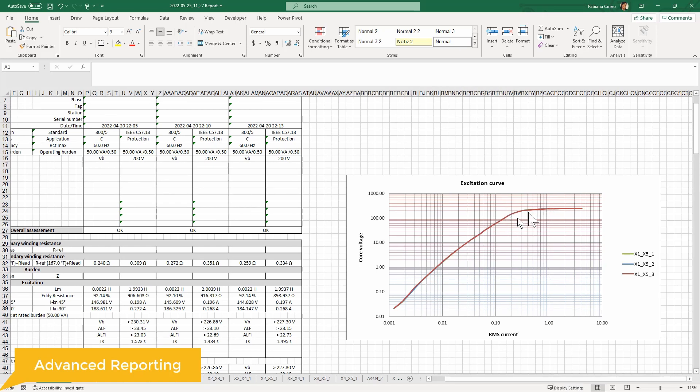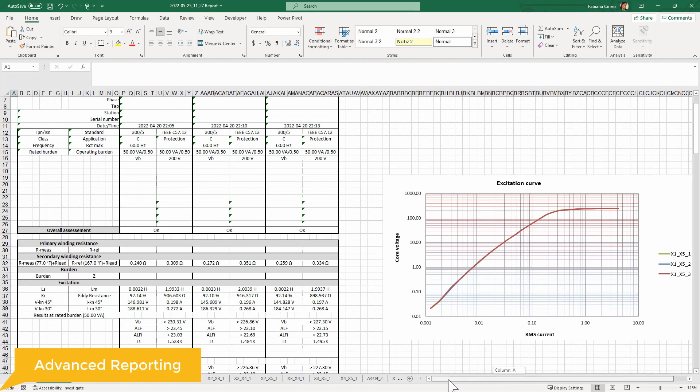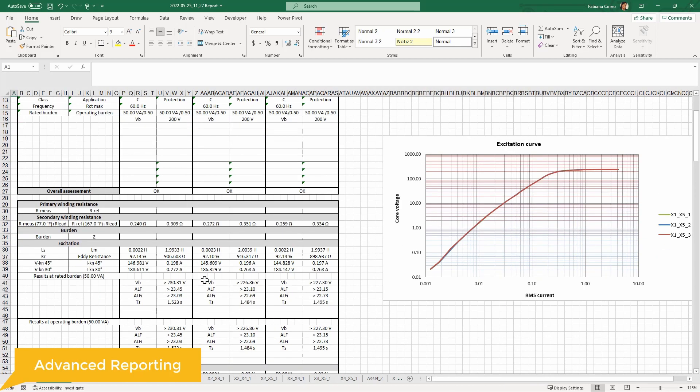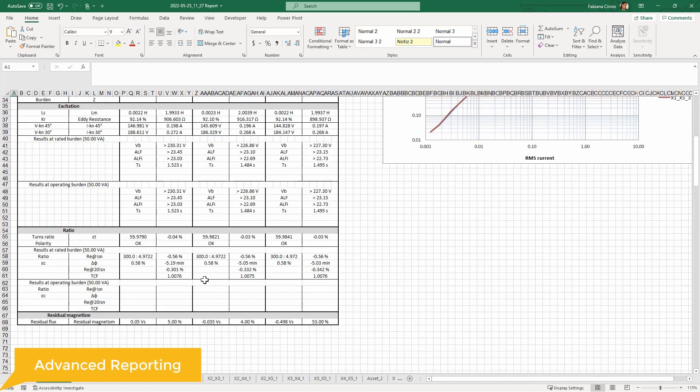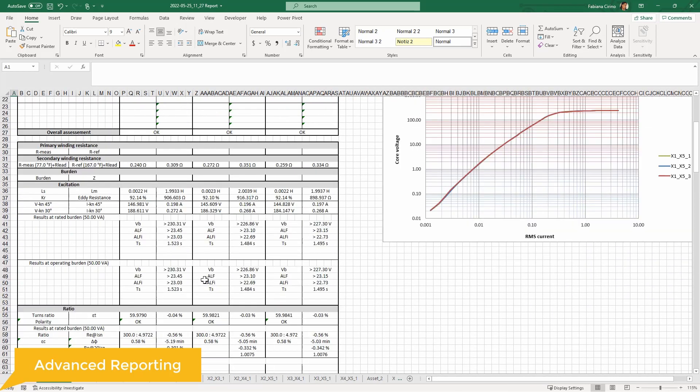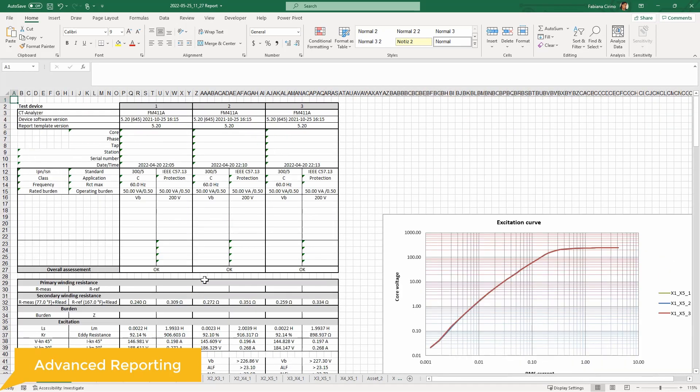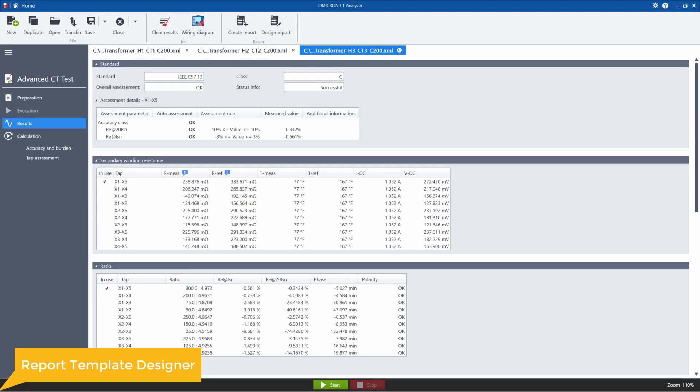So for this case, the three CTs are similar. So the excitation curves are right on top of each other. So this can be really useful when trying to further troubleshoot or diagnose your CTs.